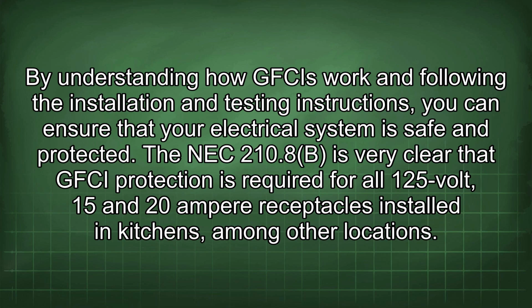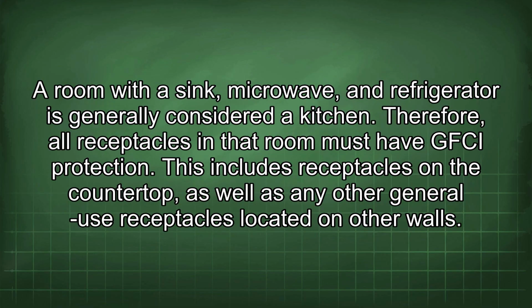ampere receptacles installed in kitchens, among other locations. A room with a sink, microwave, and refrigerator is generally considered a kitchen. Therefore, all receptacles in that room must have GFCI protection. This includes receptacles on the countertop, as well as any other general use receptacles located on other walls.